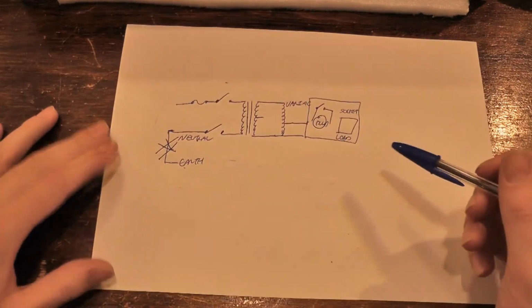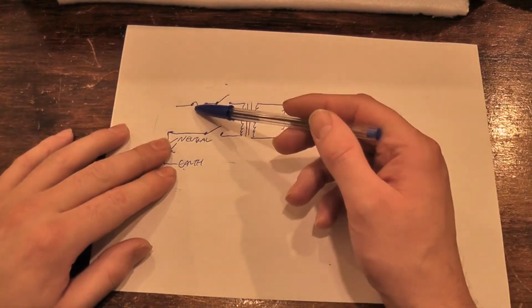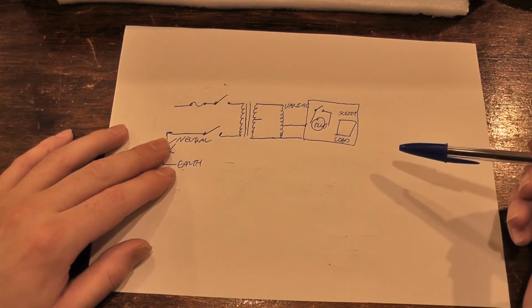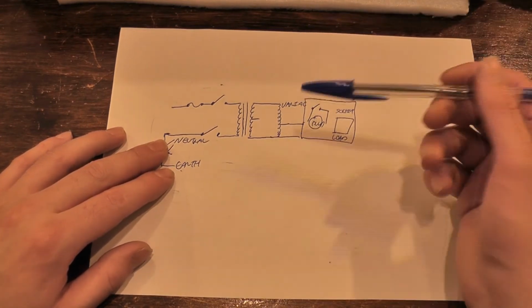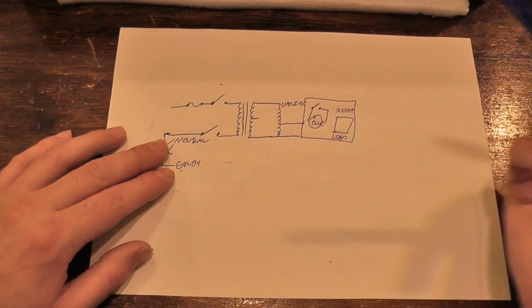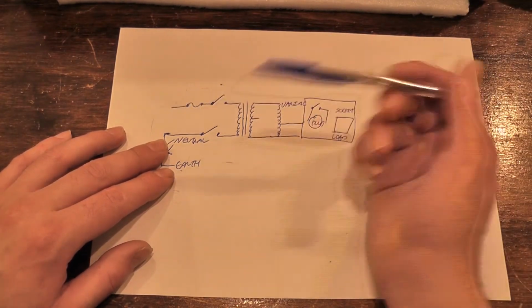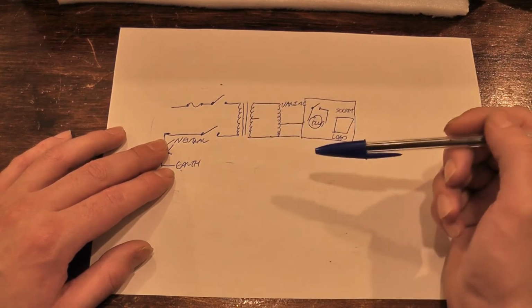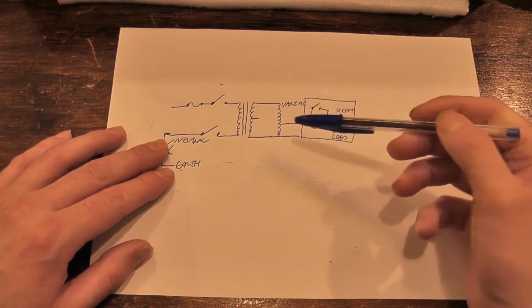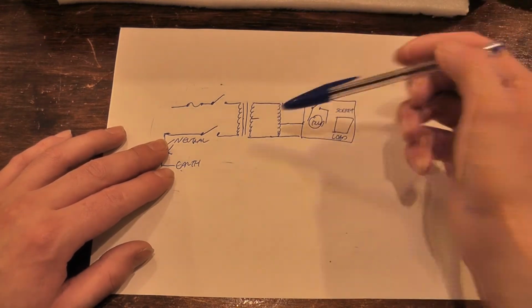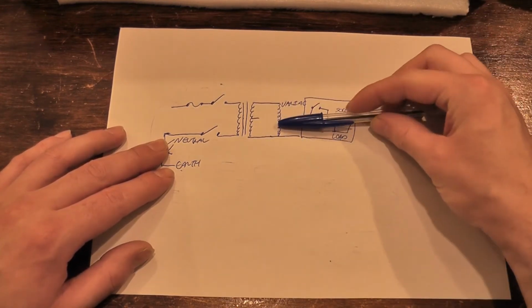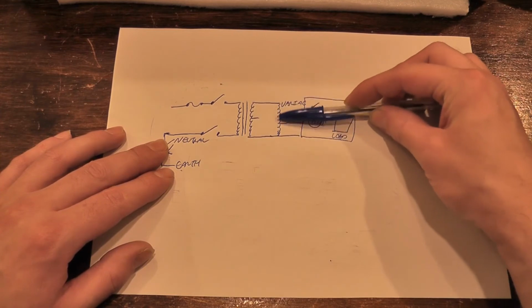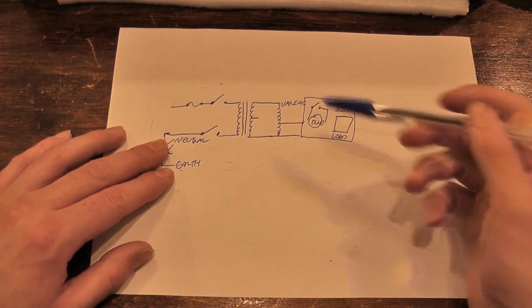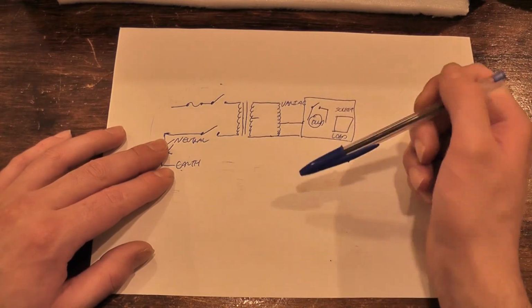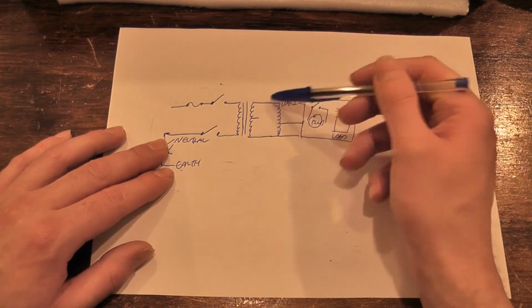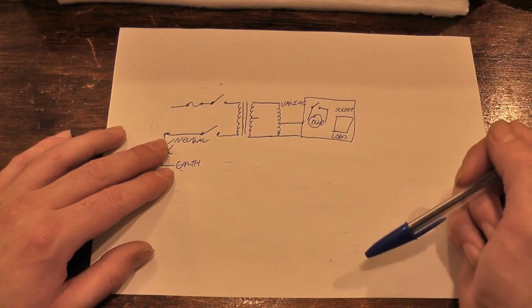Other things you can do are, if you wanted a real full versatile, robust piece of test equipment with a current limited supply, you'd have a fuse, a dual pole switch, a proper 1-to-1 ratio isolation transformer, and a variac. A variac is basically an autotransformer with a terminal that moves up and down the winding, so you can vary the actual voltage out of it. The reason you don't just have that is because it isn't an isolation transformer - there's still direct connections through this winding across to your load.